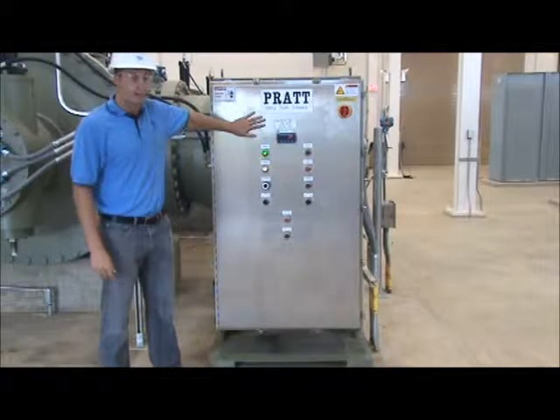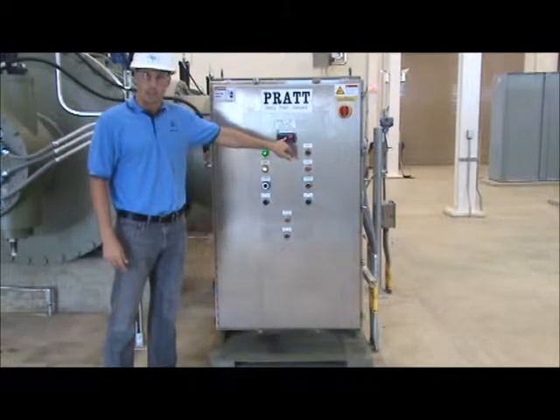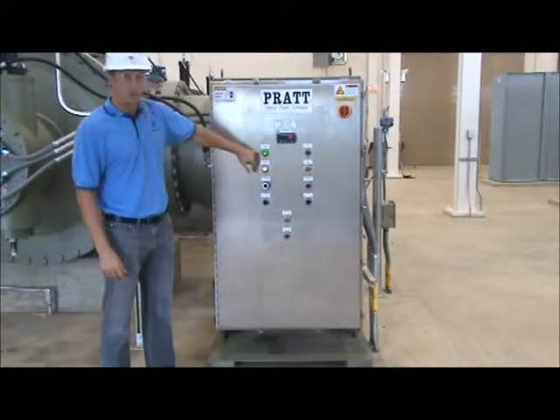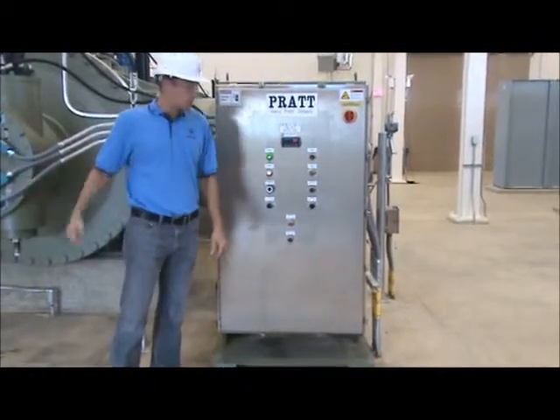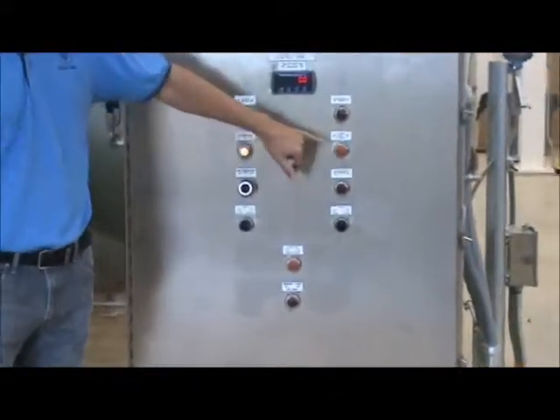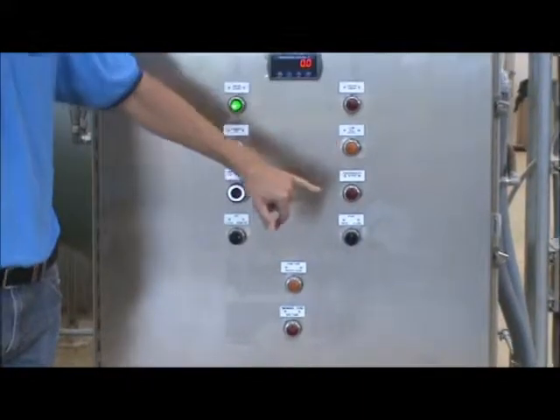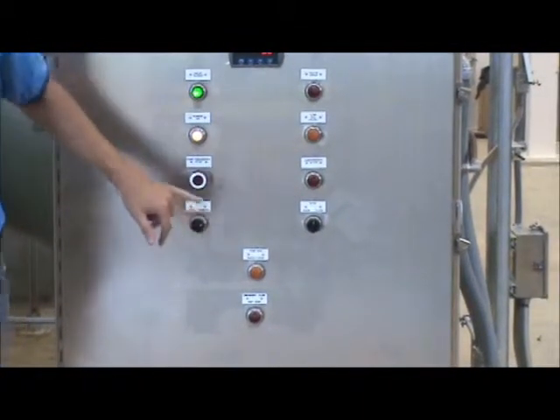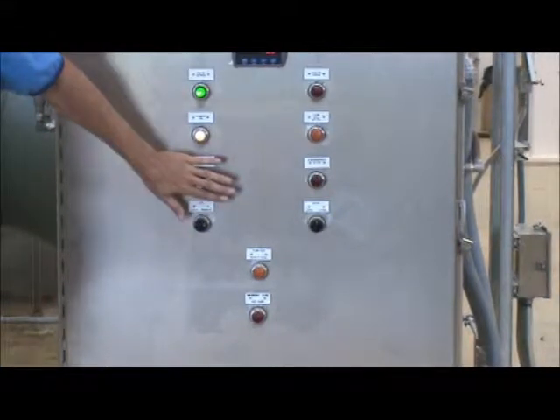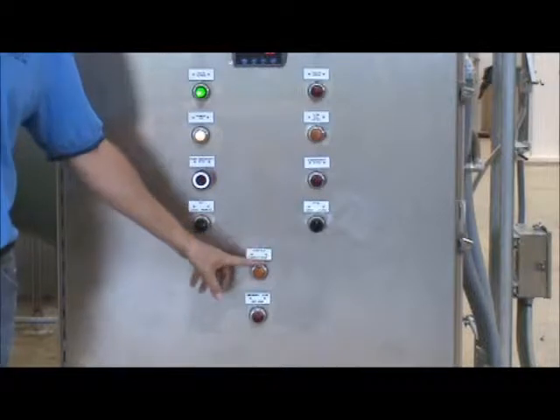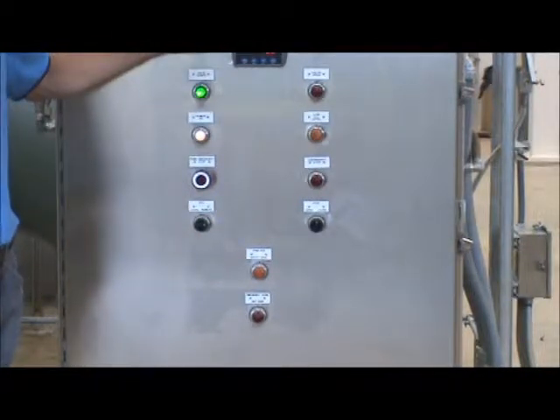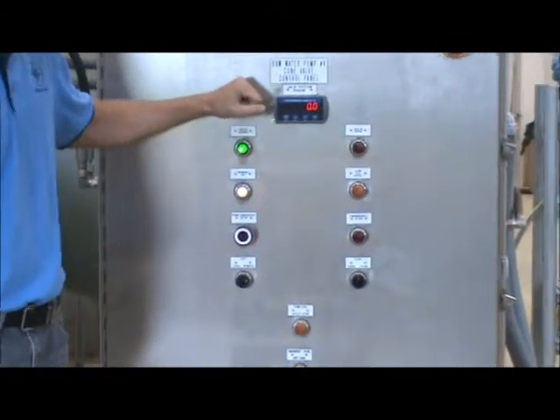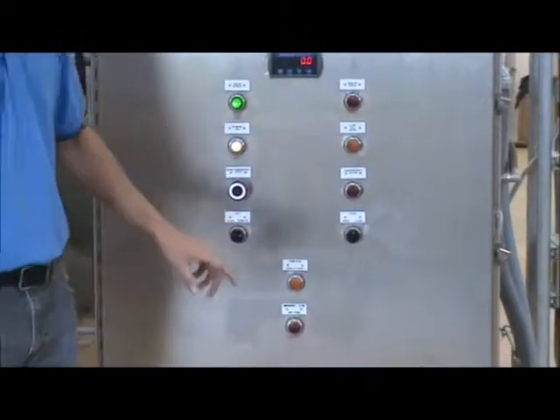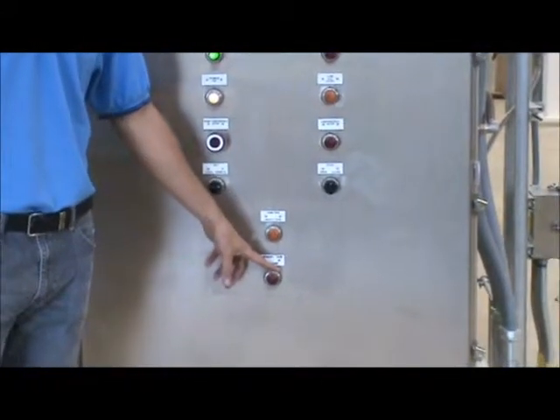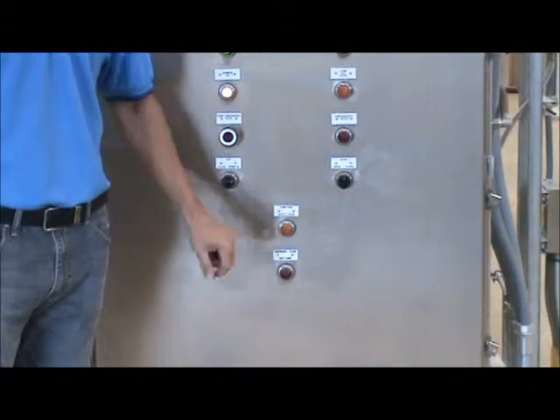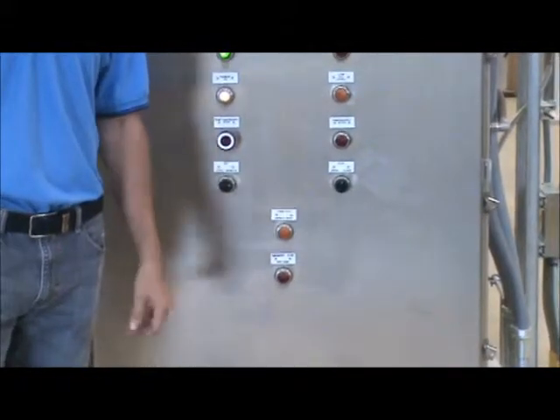This is the cone valve control panel. It has a position display that will show the percentage of valve open, valve closed, and valve open that work off the limit switches, and a power on activation light. There is a low accumulator pressure indicator, and then there's an emergency stop, as well as an emergency stop local push button here. And then there's a safety stop, which activates when either the accumulator pump has been running for too long, or the power disconnect has been thrown. And then from the soft start controller interface, we can send an emergency close signal and shut the cone valve in a fast sequence.